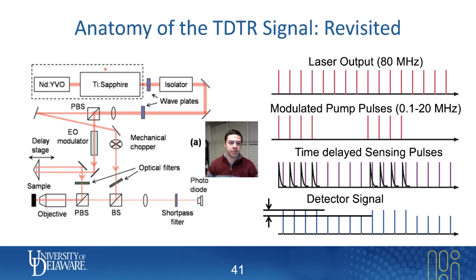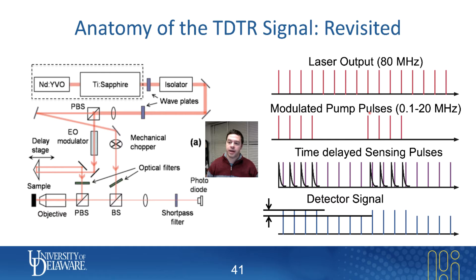In step one of our TDTR we basically created a laser output that was a train — a pulse train — of pulses coming out at 80 megahertz. We split those pulses into pump and probe at a polarizing beam splitter, and then for the pump light we modulated it. We basically turned it on and off at high speed, usually about 10 megahertz, but you control it. And so we've got periods of on and off.